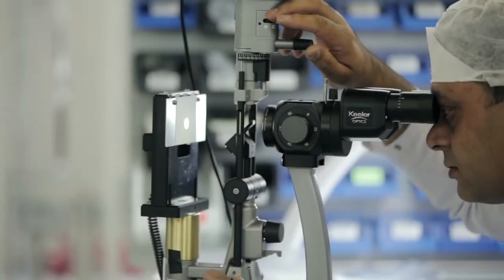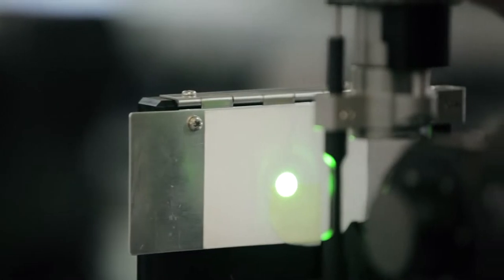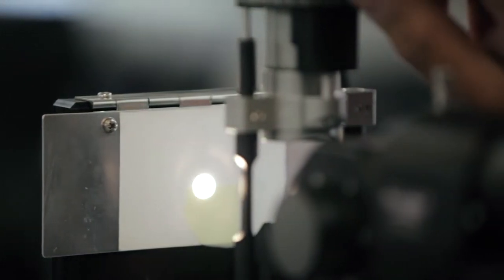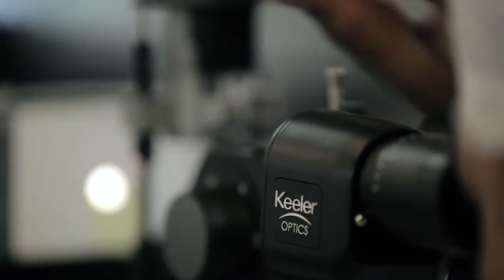The precision of the mechanics is to thousandths of a millimetre and we're dealing with alignment of the optical system to hundredths of a degree. Looking at the outcome of the design, the product is now exceeding our original design specification. We've incorporated a unique feature from our portable slit lamp — the one millimetre square — which helps in the assessment of uveitis.